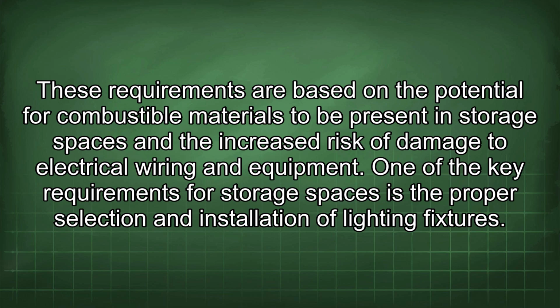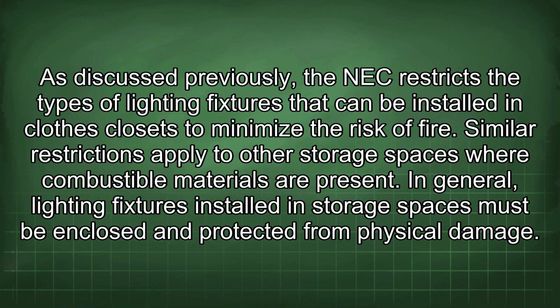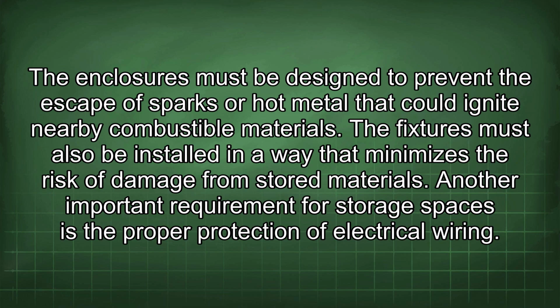One of the key requirements for storage spaces is the proper selection and installation of lighting fixtures. As discussed previously, the NEC restricts the types of lighting fixtures that can be installed in clothes closets to minimize the risk of fire. Similar restrictions apply to other storage spaces where combustible materials are present. In general, lighting fixtures installed in storage spaces must be enclosed and protected from physical damage. The enclosures must be designed to prevent the escape of sparks or hot metal that could ignite nearby combustible materials. The fixtures must also be installed in a way that minimizes the risk of damage from stored materials.